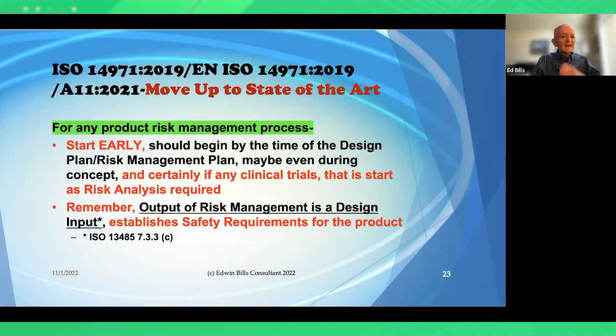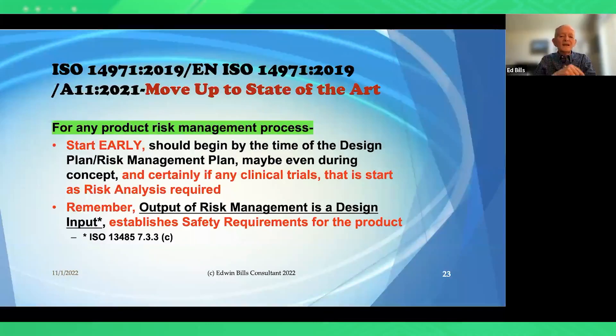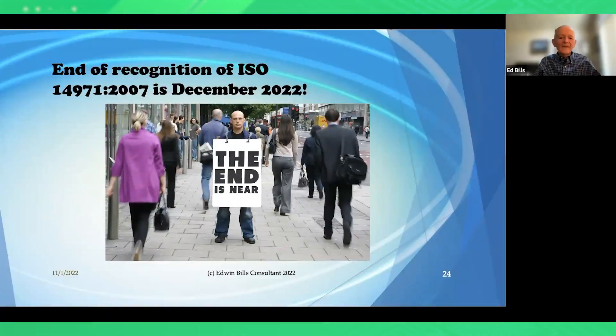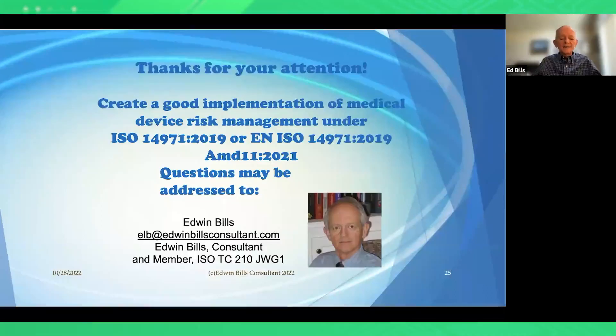For any risk management process, you should start early — by the time of design plan creation, maybe even during concept development, and certainly during clinical trials since clinical trials require risk analysis. The output of risk management is design input. The end of recognition of ISO 14971-2007 is December 2022. Scrub all documentation and remove any references to earlier editions. You should have either the ISO 2019 or the EN 2019 version — the EN version needs to include Amendment 11 from 2021.